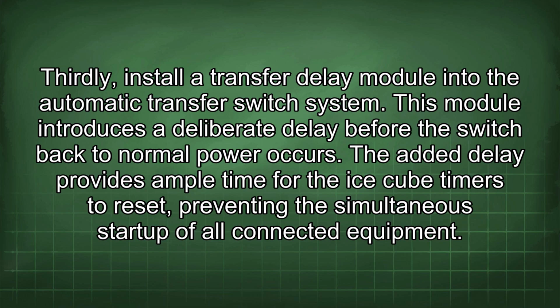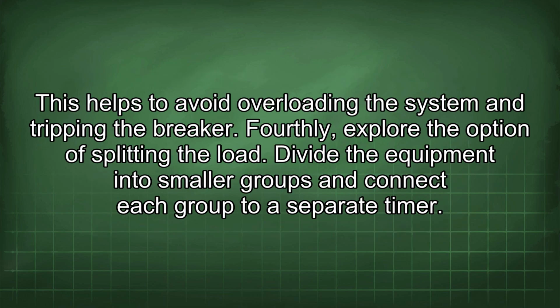Thirdly, install a transfer delay module into the automatic transfer switch system. This module introduces a deliberate delay before the switch back to normal power occurs. The added delay provides ample time for the ice cube timers to reset, preventing the simultaneous startup of all connected equipment. This helps to avoid overloading the system and tripping the breaker.